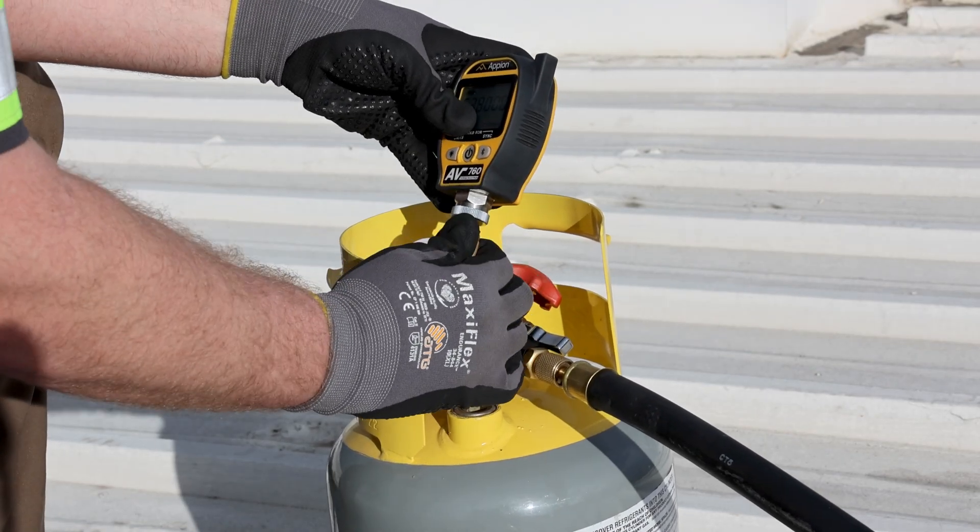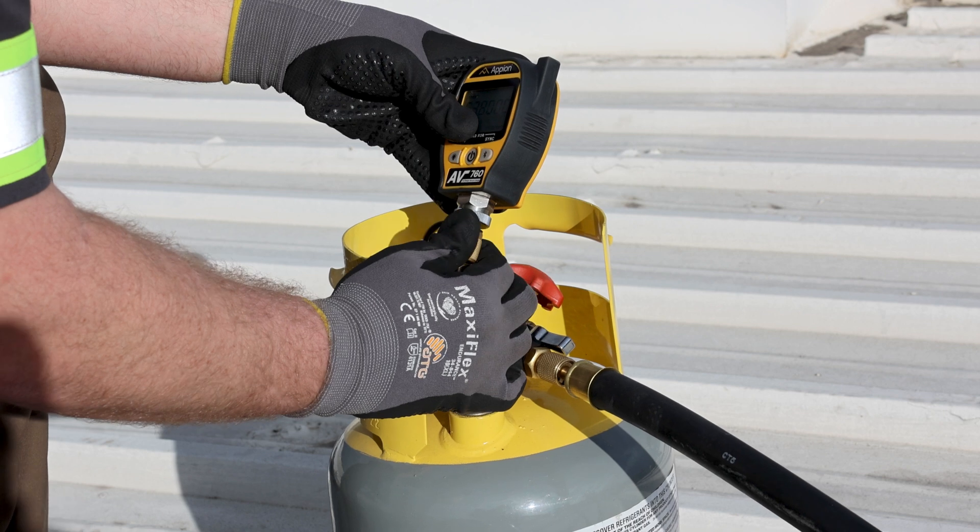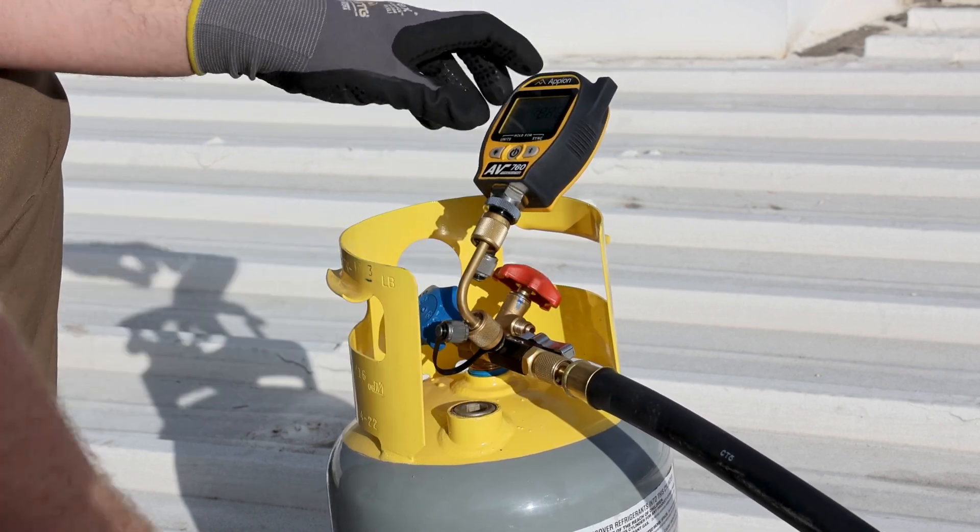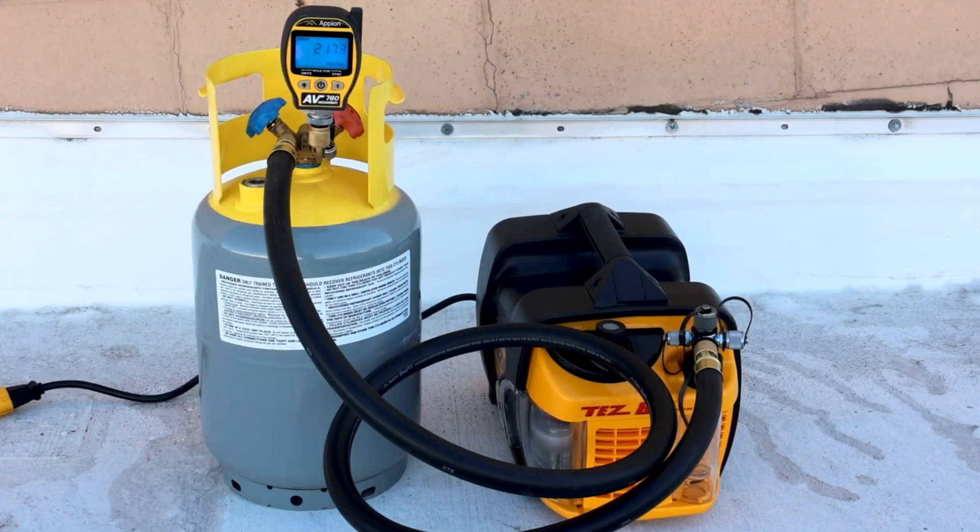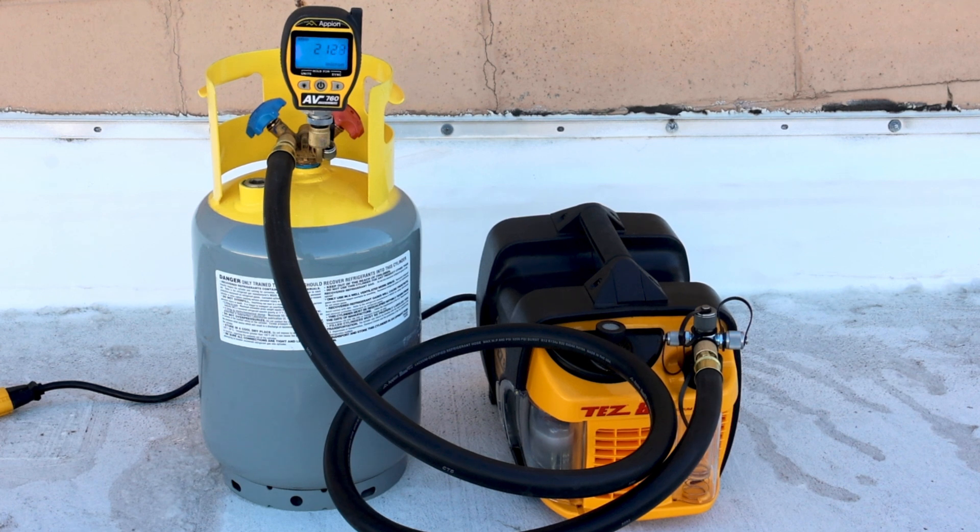However, you will want to evacuate the cylinder to ensure there is no moisture or contamination that could negatively affect the refrigerant. A well-evacuated cylinder also aids recovery by creating a low-pressure area for the refrigerant to migrate to at the beginning of the recovery process.